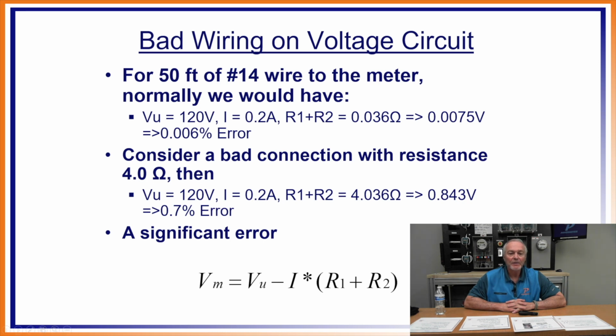But wait a minute. What if we add, through either a bad connection or too large a size of wire, which we're talking about in a minute, some more resistance in there? Now instead of 0.036 ohms, and if you've done a burden measurement out in the field with our equipment, these are the ones where you go, uh-oh, you see all of a sudden that you've got way too much burden there, which is resistance. So you can measure it with the equipment now. Instead of the 0.036, I've got 4.036. That's 0.7% error, which is definitely a significant error. If I have a bad connection, those numbers do jump significantly. When you're out there in the field doing a burden measurement with our equipment, you're going to see that. When it's a bad connection, loose connection, or broken wire, it doesn't just ease up a little bit. It will be a significant change in the amount of resistance, something similar to the good example Steve gave here.